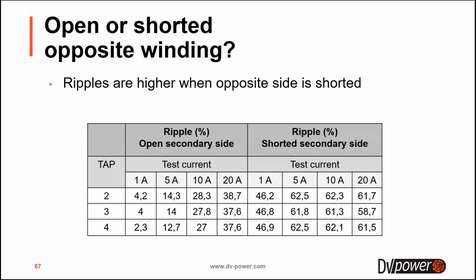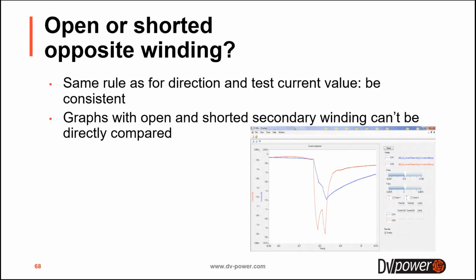So the ripples, we said, are higher when the opposite side is shorted, which you can see here on this table. And you can also see here a direct comparison of graphs when the opposite winding is shorted, that is the red graph, and when the opposite winding is open, the blue graph. The timing is the same, you still have characteristic parts of the graphs, but you cannot directly compare the graphs. That's why it's important, again, to be consistent. If you have reference benchmark results with open opposite winding, then in the future do the testing with the open opposite winding. And of course, if the benchmark results are recorded with shorted opposite winding, you will do your next measurements with the shorted opposite winding, so you can directly compare them.